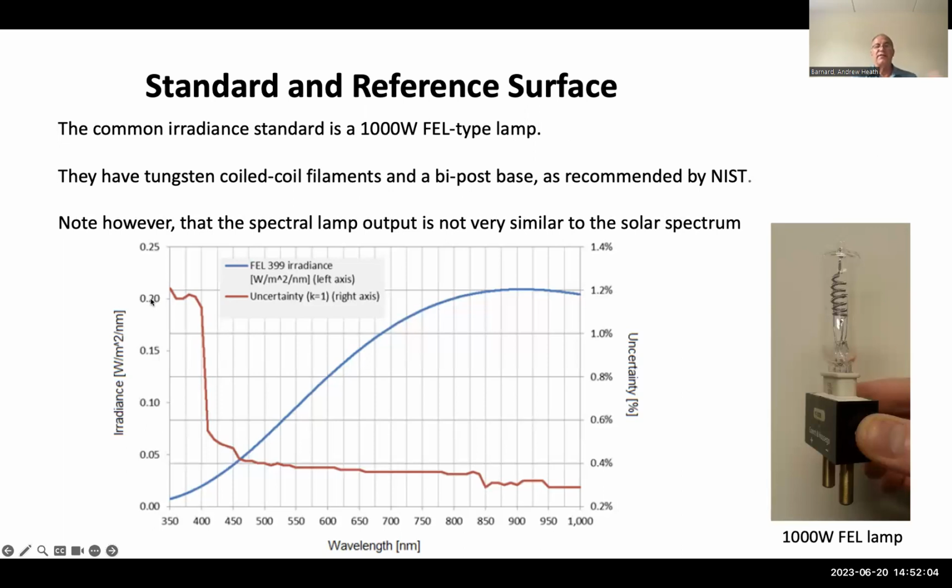So this is one of the factors we talked about, in terms of why it's hard to calibrate and why there's so much uncertainty in the calibration process. As you get lower and lower, and the less light flux you're getting from the blue region, the more uncertainty you're going to have in that calibration coefficient.